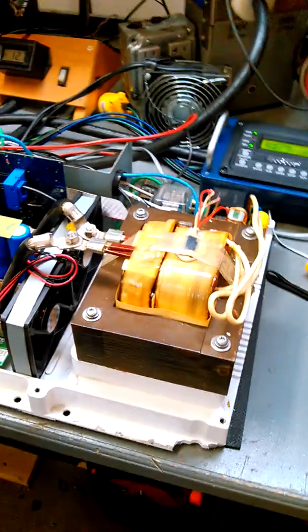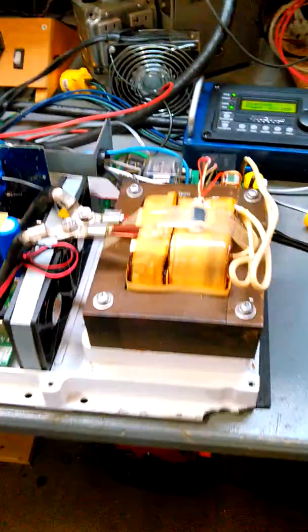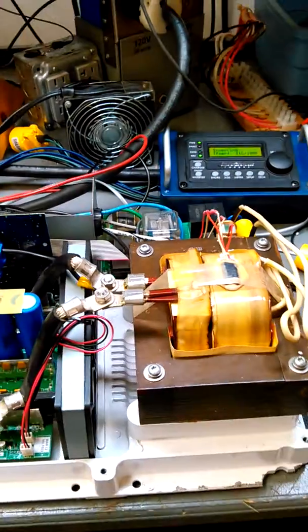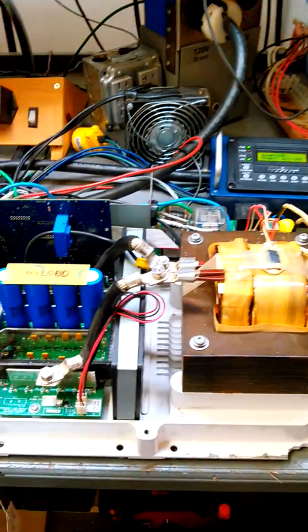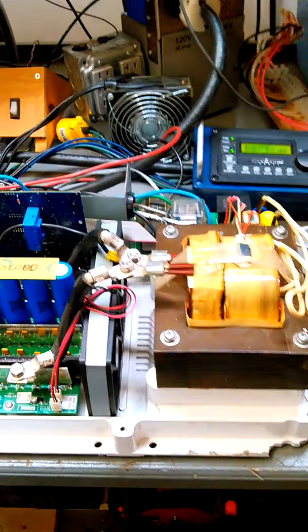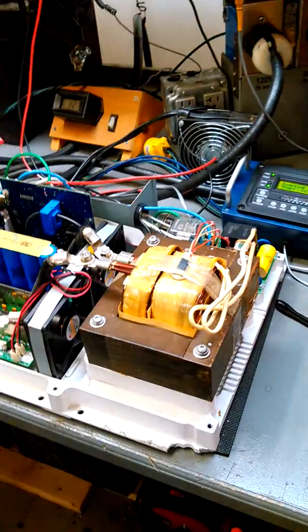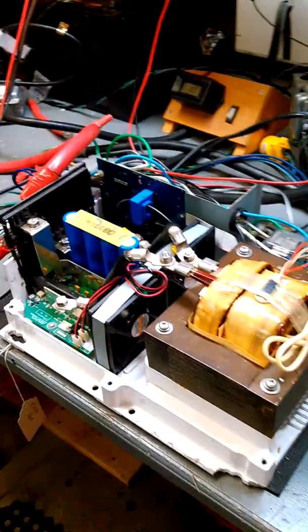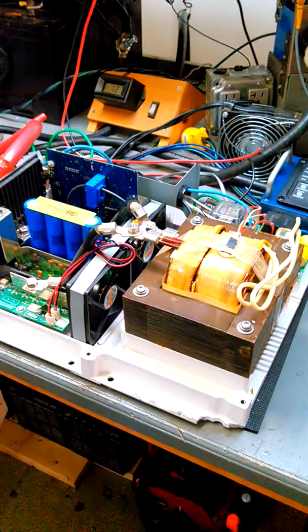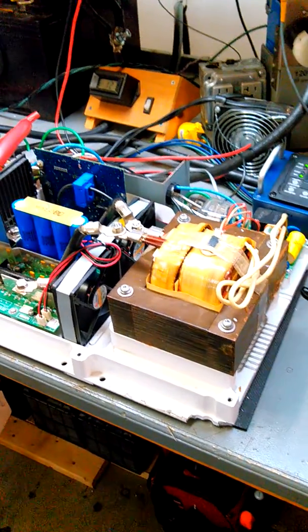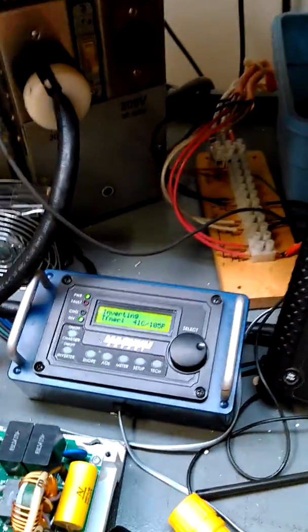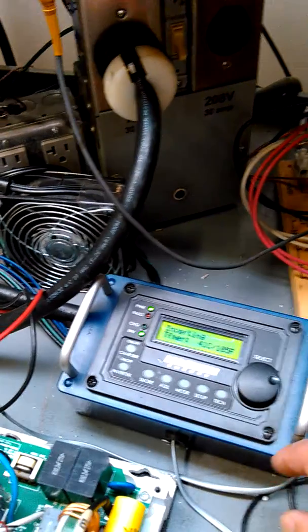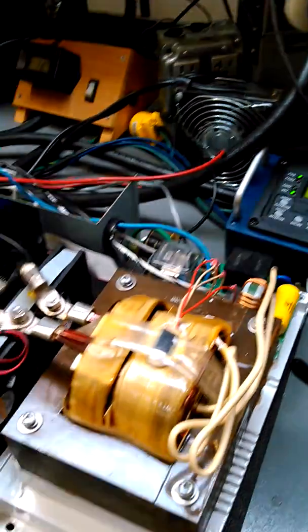This transformer we've noticed will run a little hotter than some of the other ones. The whole unit in fact runs a little hotter. So on these units we often recommend that you don't use the full 100% charge cycle. These units will get, this is typical of Magnum inverters, they get hotter during charging than they do inverting.